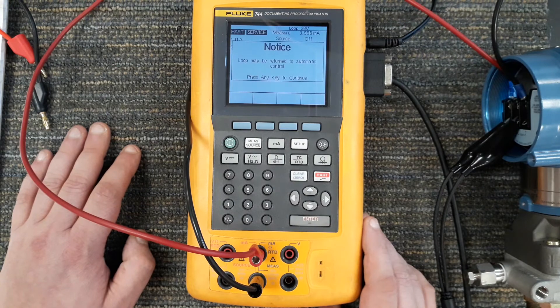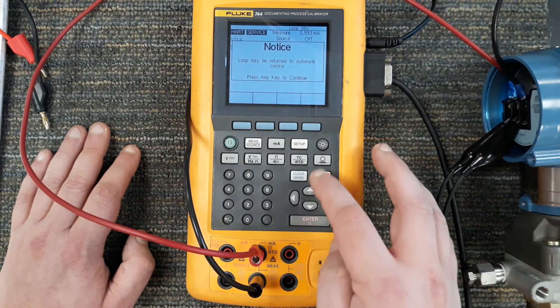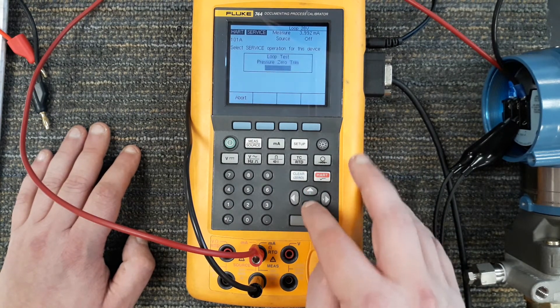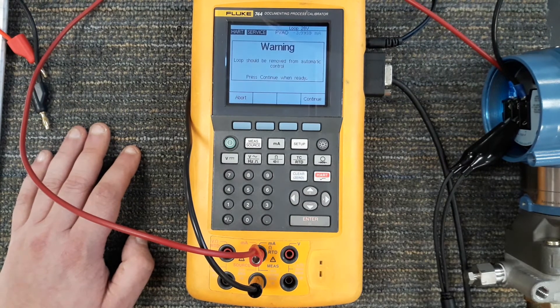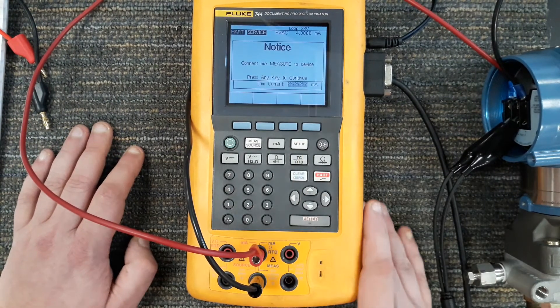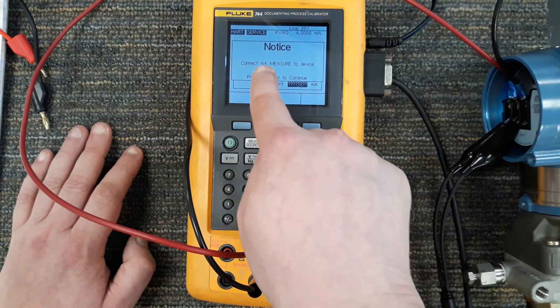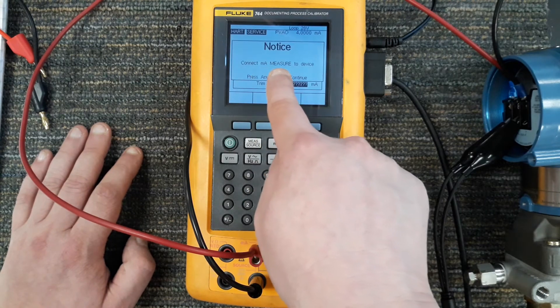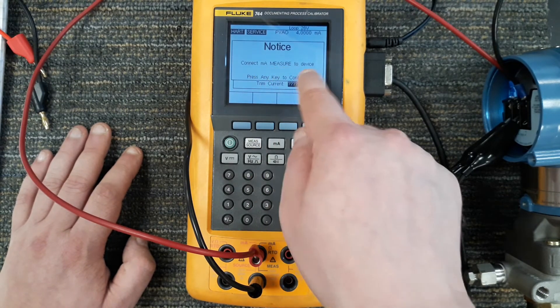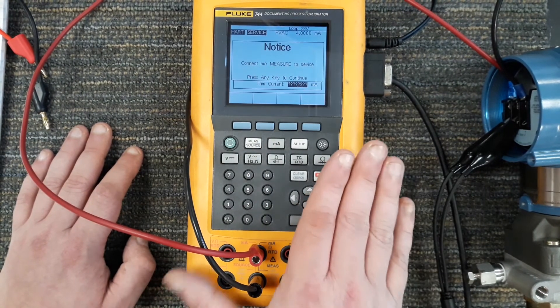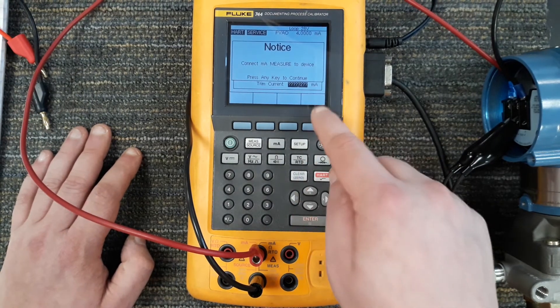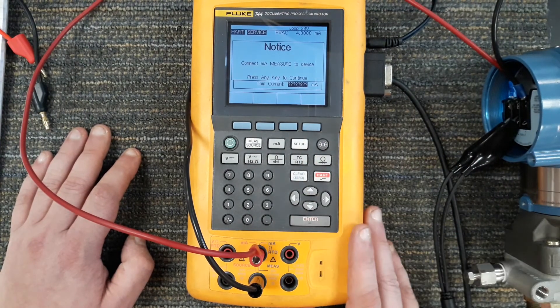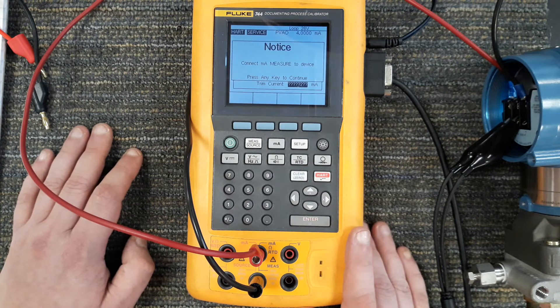Exiting loop test, press any key. Of course, output trim. We could perform output trim, but it says connect a milliamp meter to the device. I'm providing this loop power from this, so it's telling me you gotta hook up another measuring device to measure your current to actually perform this output trim. I'll hit abort on this.